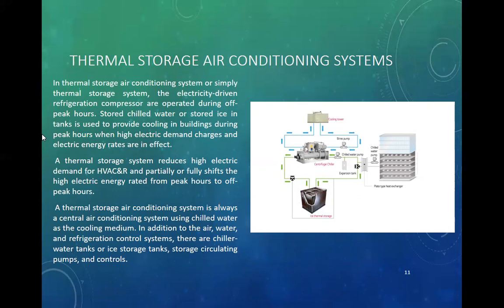So, and thermal storage air conditioning system or simply thermal storage system. The electricity-driven refrigerators and compressors are operated during off-peak hours. Stored chilled water or stored ice in tank is used to provide cooling in building during peak hours when high electric demand charges and electric energy rates are in effect. So, kakatipid nila. Hindi siya in full. A thermal storage system reduces high electric demand for HVAC and R and partially or fully shifts the high electric energy rate from peak hours to off-peak hours.